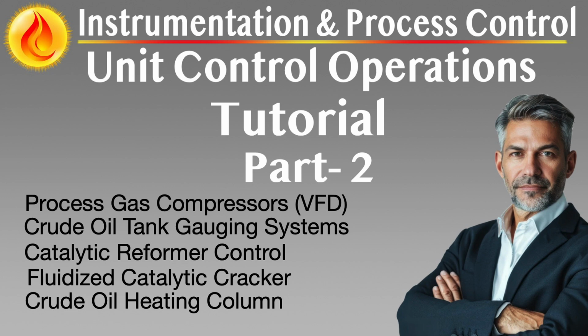The regenerator removes coke deposited on the catalyst during cracking through controlled combustion, generating the heat needed to drive the process. Airflow to the regenerator is managed by oxygen trim systems, burner management logic, and high-speed mass flow controllers. In advanced units, two-stage regeneration, dense and dilute phase control, is implemented using smart thermocouples, oxygen analyzers, and CO-CO2 ratio monitoring. MPC algorithms balance coke burn, heat generation, and catalyst activity to maintain steady reactor temperature and avoid afterburn or CO breakthrough. Feed rate control in FCC is not simply a function of upstream supply.